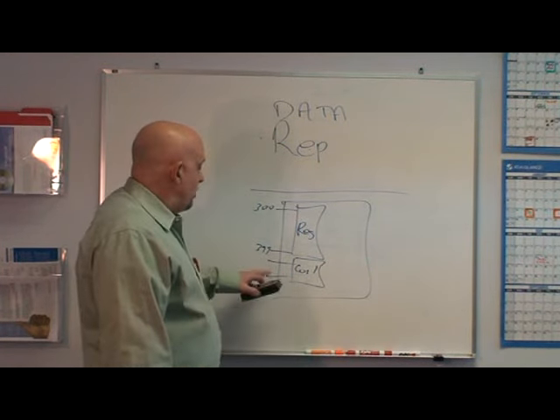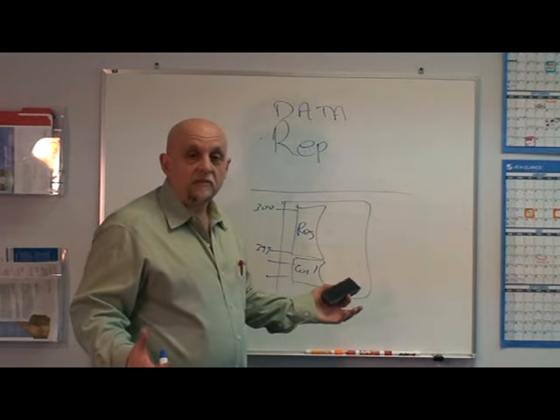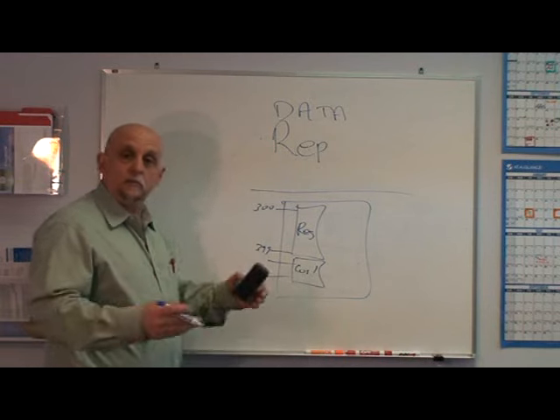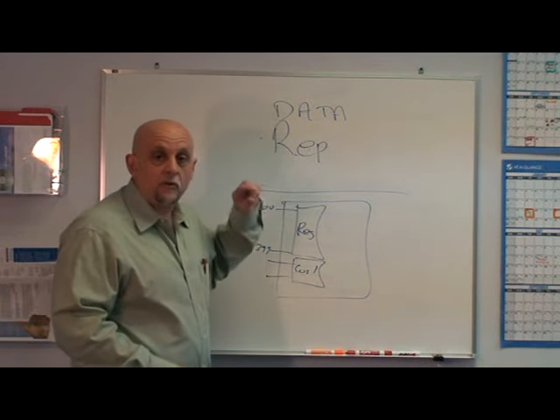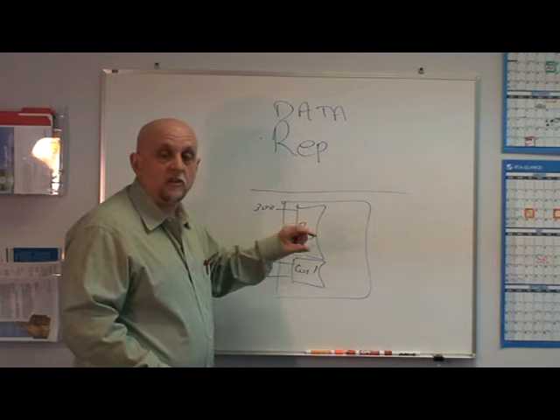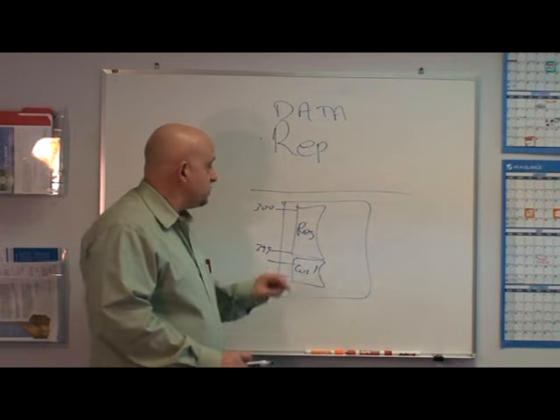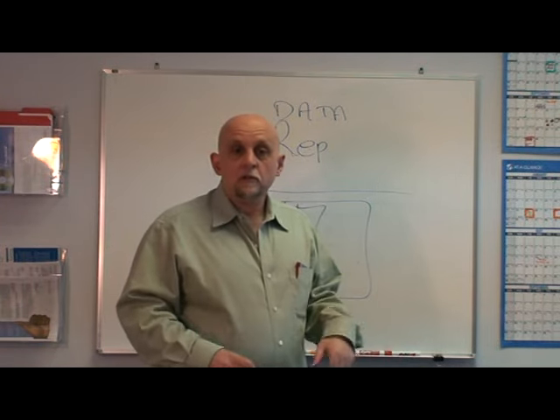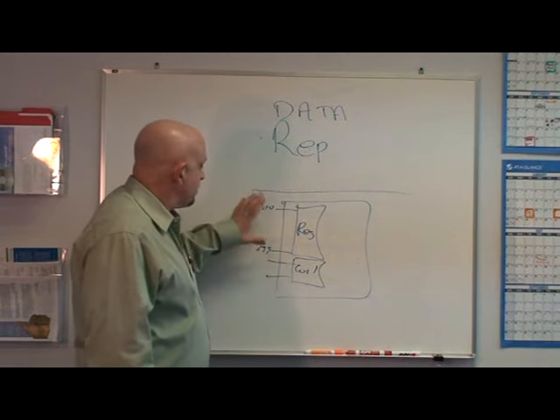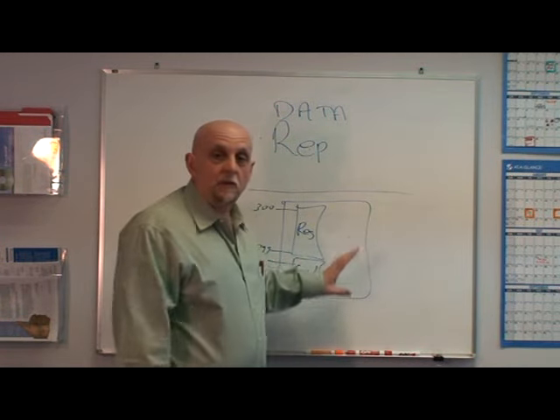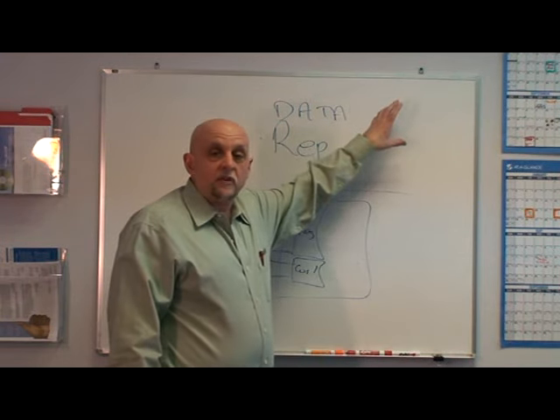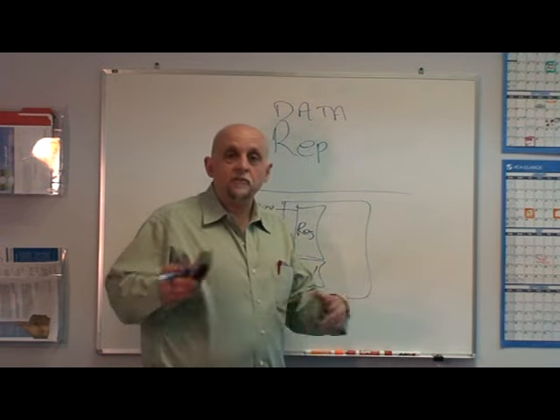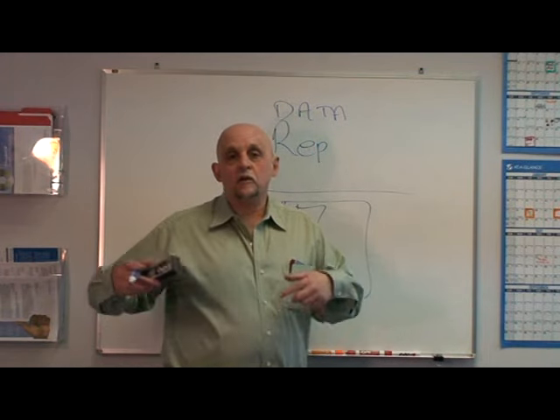So also for registers and coils, you've got actually 64K of space that you can allocate for input registers, holding registers, input coils, status coils, whatever you want. So you've got a lot of space, but most people just take a small segment of it because they've got very small amounts of data and say, I want to use 10 registers. I'm going to start it at this point and end at this point. Now that's real simple, but it's also the biggest downfall of Modbus. Downfall because every device is different. This designer picked this representation, another designer doing the same kind of thing will pick a totally different representation. He'll use 50,000 as the address for 10 registers. This guy used 300 for the address of 100 registers. So nothing matches, meaning that you've got to switch from one Modbus device to the next, you've got to reprogram your system.